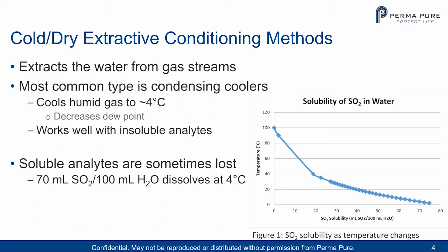So the most common way that the water is removed from sample streams is with a condensing cooler. That cools the humid gas to 4 degrees C and decreases the dew point of the sample gas also to 4 degrees C. This works well with insoluble analytes. So if you're measuring CO2 or other types of analytes that are not soluble in water, this is not an issue because it takes the water out reliably and effectively.